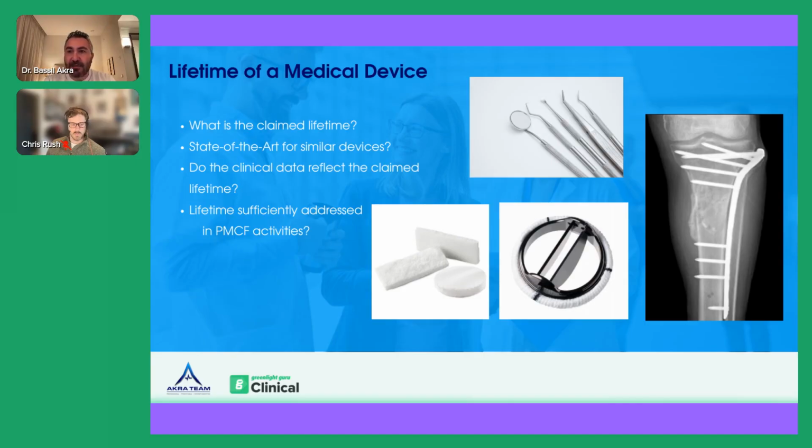And like I said, the post-market clinical follow-up is actually a principle which has a relationship to your expected lifetime that you have defined for your device, and or the effect of your device on the body. So if you have an absorbable device which will be absorbed within 30 days, it doesn't mean that the lifetime is 30 days, because that absorbed material might remain in your body for at least 6 months or 1 year. So your safety measure will not be just after 30 days.